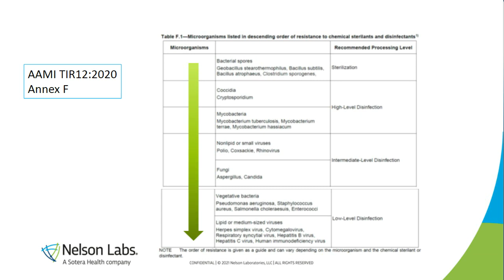The previous version of TIR12 focused on patient contact and the Spalding classification to determine what level of disinfection or sterilization was needed. So if a device contacts sterile areas of the body, that is a critical device, and sterilization is required. Likewise, devices that contact mucous membranes or non-intact skin are designated as semi-critical and ideally would be sterilized, but if sterilization is not compatible with the device, either due to materials or electrical components, a high-level disinfection can be performed. And then finally, devices that contact intact skin or have no contact with the patient are designated as non-critical and need either a low-level disinfection or an intermediate-level disinfection.